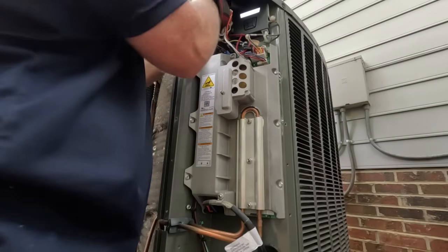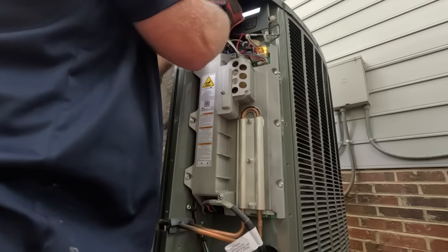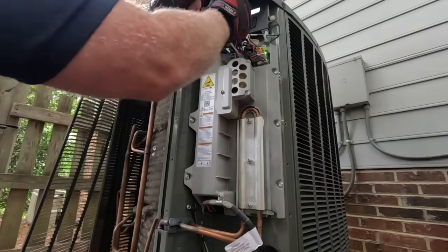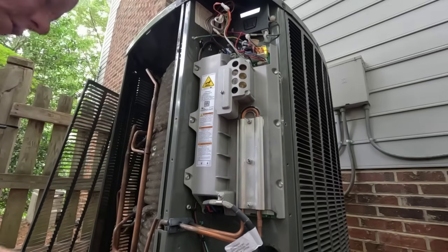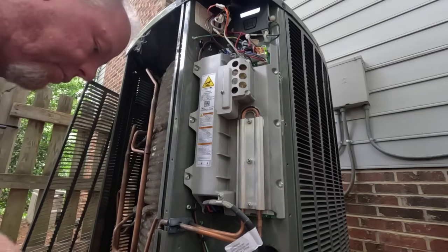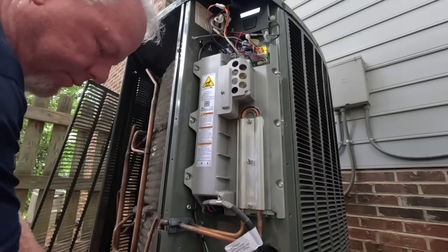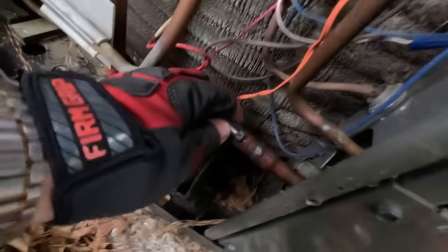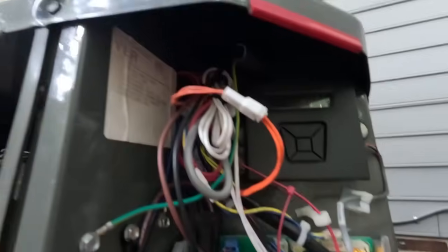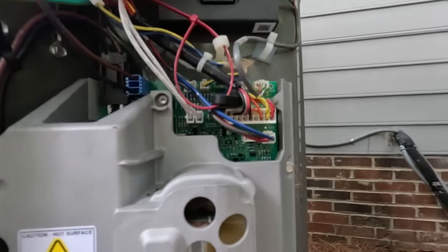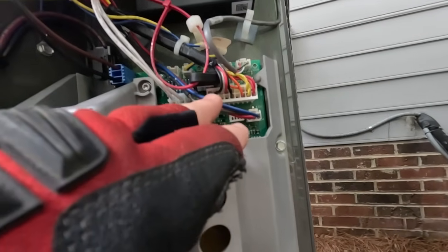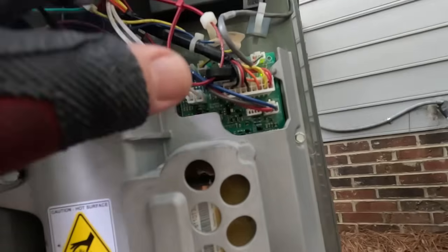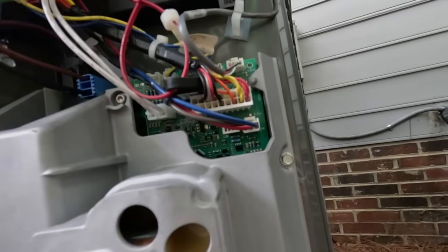Getting the plug back through this little hole up here is the hardest part of swapping it out. Well, that one wasn't so bad. So we will plug it back together, and I will snap this back onto the suction line. Right there is where it goes. It plugs in, everything in here kind of plugs back in and feeds to this main terminal on the top of this thing. The ambient sensor, the suction pressure transducer, the coil temperature sensor, but there's not one in this unit, so there's not going to be one plugged up to that. The heat pump version has that for the defrost control part of it.